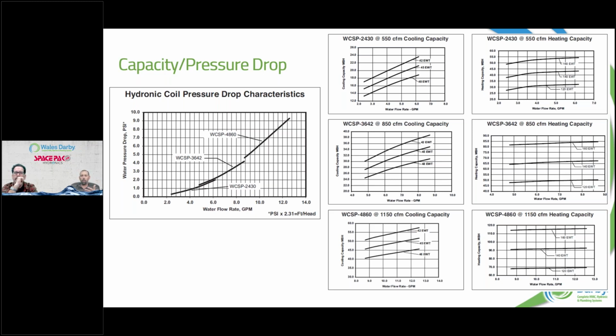And we knew we were getting this complaint where just on really cold days, we weren't getting the performance out of the system. We knew, when we looked at the load calculation, the desired water temp we wanted to use, how many BTUs we should be able to get. We just weren't getting it, so we ended up putting some circuit setters on there. I got some samples for that project, and we were able to dial into GPM.